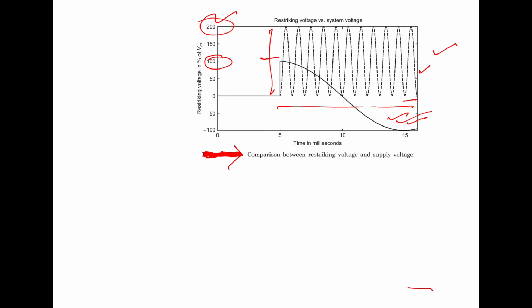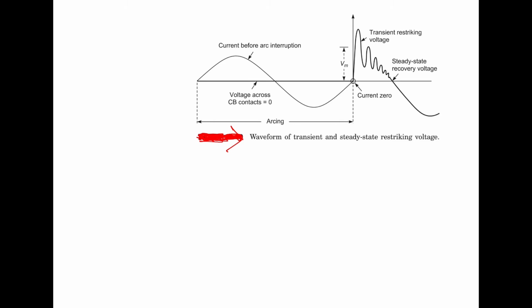This is the model in which we have assumed that L and C are there in the circuit. However, let us suppose that we have resistance in the circuit. When we include the resistance, the restriking voltage will die down in due course of time, as shown in the figure. So it will have the damped natural frequency. First we will have the current before the arc extinction, and after that, when it is interrupted at current zero, then definitely this transient will die down, and so this is more realistic. Now this is the restriking voltage, so we have to find the rate of rise of this restriking voltage.